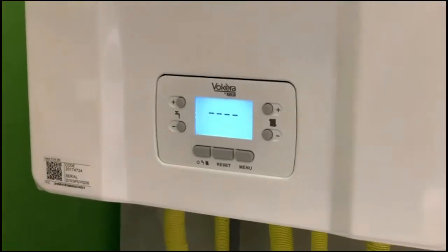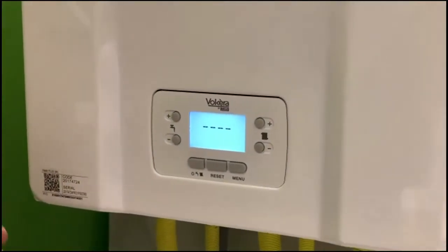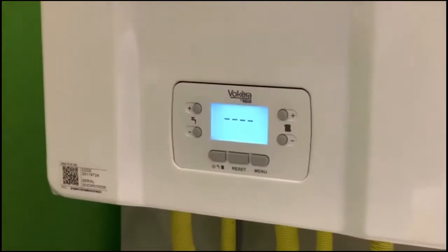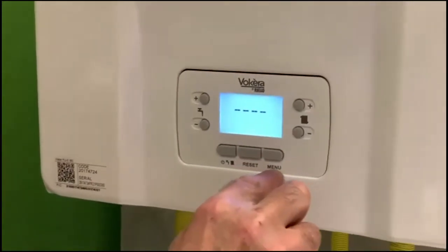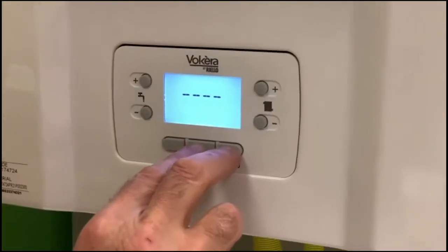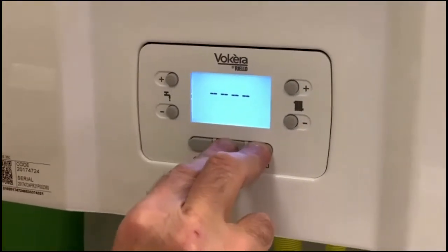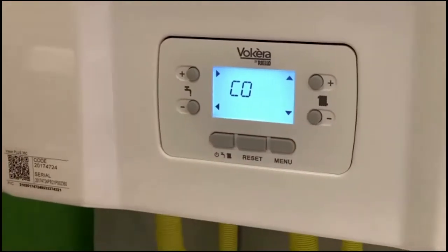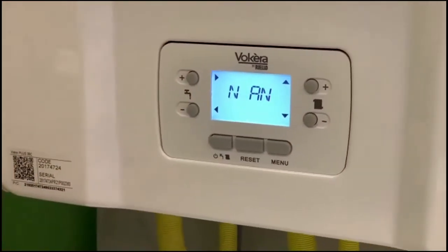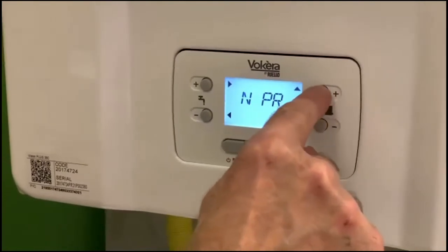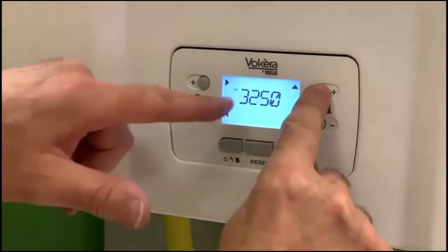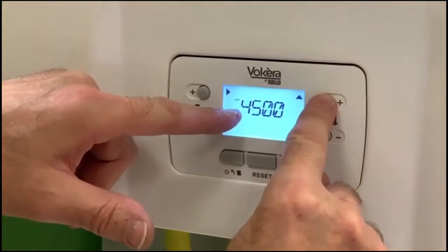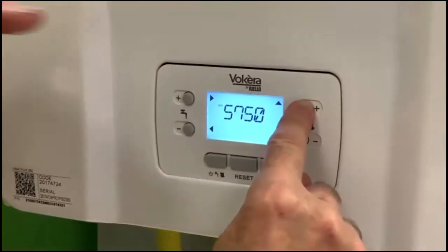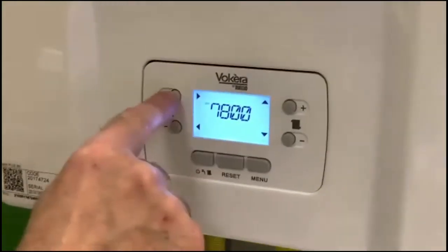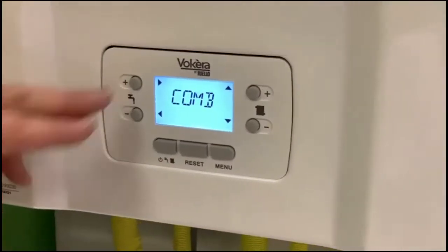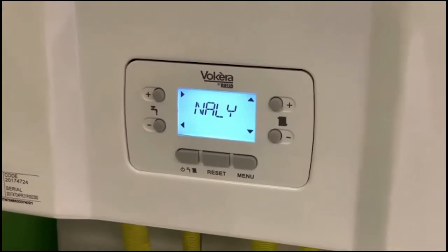How to get the Vision Plus into CO mode. I'll show you the procedure, but I won't actually flue gas analyze the boilers. To start the procedure on this boiler, we have a reset and a menu button. Press and hold reset and menu. Boiler starting to fire. Combustion analysis. Now press the plus button on the right to raise the fan speed to absolute maximum. It won't go above the maximum. When you've hit it, press top left to confirm. The boiler will now run at maximum.